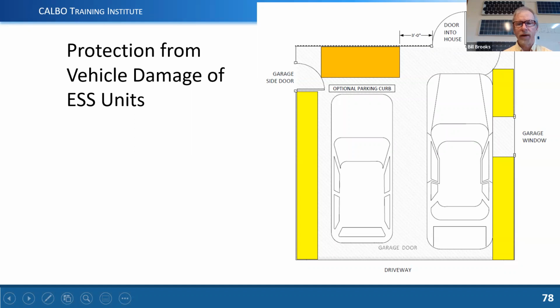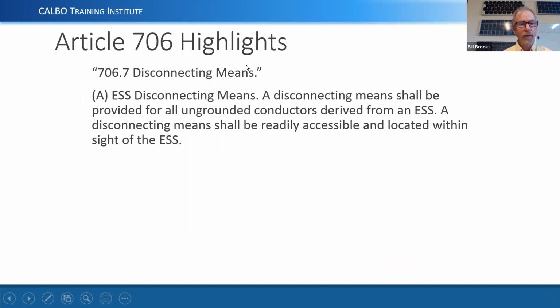and then of course the height could work as well. The reason we're not allowing anything over here is because it's within 3 feet of a door entering the dwelling unit. This interface door is entering the dwelling unit. We can't get within 3 feet of that, so that basically makes this whole area not allowed. Okay, so it's just some examples.